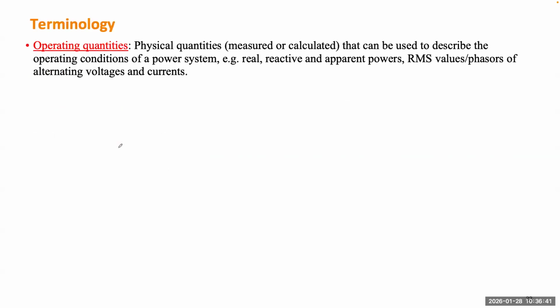The first one is operating quantities. Because we need to study the security, dynamics, and stability of the power system. A power system has many variables or parameters, and we as engineers or operators don't need to check every single variable. They only select some of them which are almost enough to represent the security or reliability condition of the system. Usually such quantities are power, real power, reactive power, apparent power, or voltage and current. For voltage and current, they measure the RMS value, the root mean square value, and the phasor value. So basically power, voltage, and current of the system will be the most important ones to monitor and to check the reliability of the system.